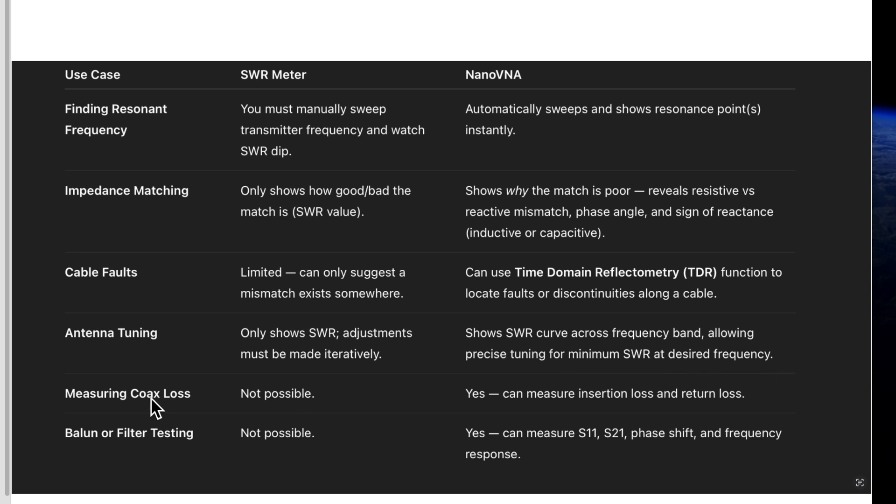Measuring coax loss, not possible with an SWR meter. Nano VNA can measure insertion loss and return loss.